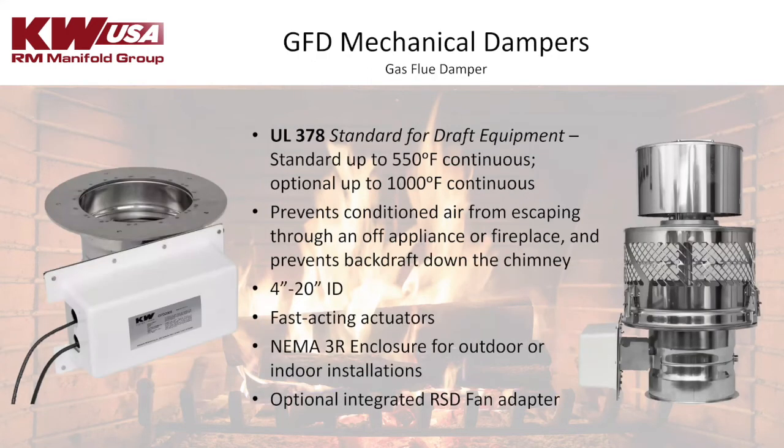These are our GFD mechanical dampers, so gas flue dampers. They are, of course, listed to UL 378. The standard model is listed up to 550 degrees continuous, but there is an optional high temp version up to 1,000 degrees continuous. So basically, why install a mechanical damper? Well, it prevents conditioned air from escaping through the flue of your off appliances or fireplaces. It also prevents backdraft down the chimney when that fireplace or appliance is off. So it improves the efficiency of the air in your house.